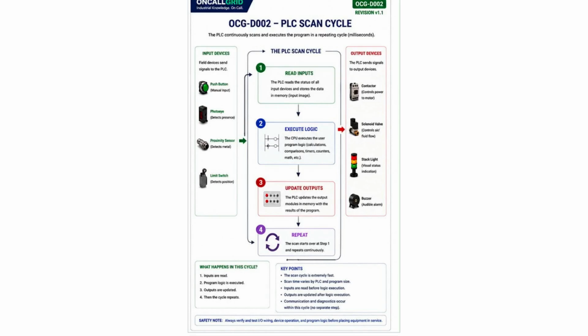So if an input never seems to change on, don't jump straight to blaming the PLC. Work it in order. Measure the 24 volts, check the sensor's own LED, verify wiring continuity, watch the PLC's input LED, and only then start suspecting the input itself.